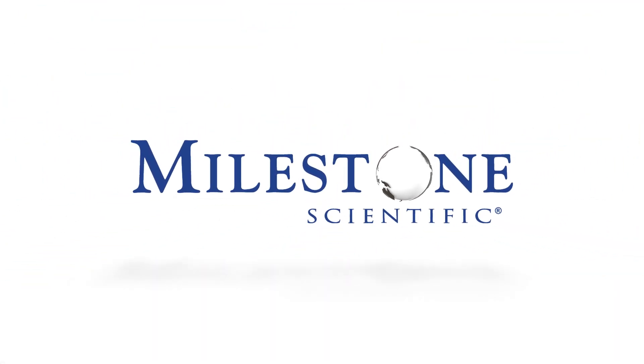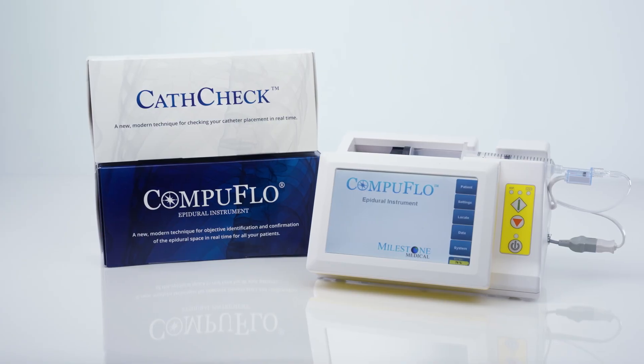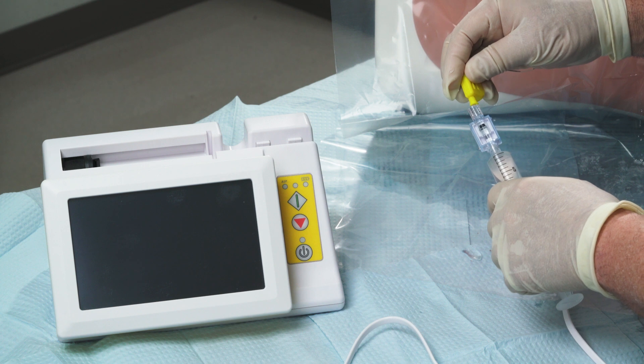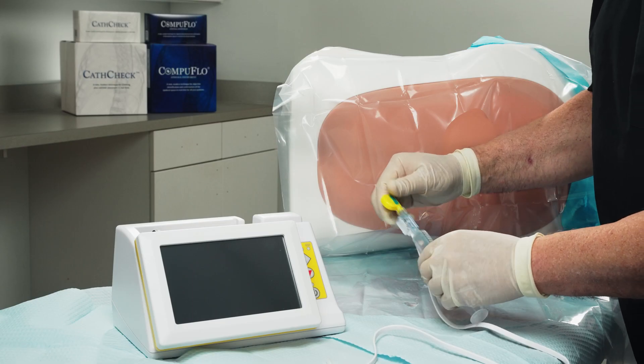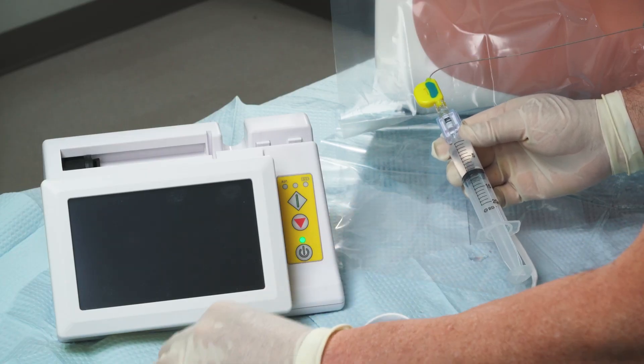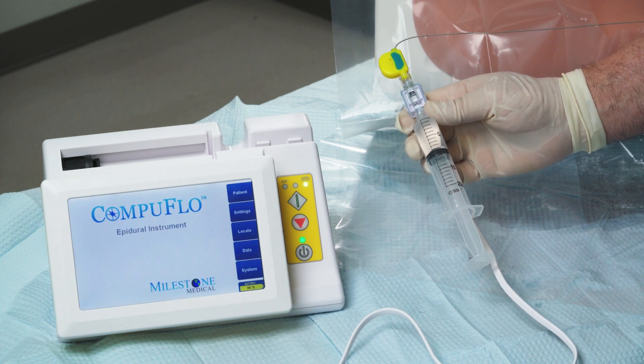Milestone Scientific is excited to announce the CathCheck Verification System to be used with the CompuFlo Epidural Instrument. CathCheck Verification System monitors the pulse wave in the epidural space and may be used to confidently verify and troubleshoot pre-existing indwelling epidural catheters by providing objective data to complement the provider's own knowledge and expertise.